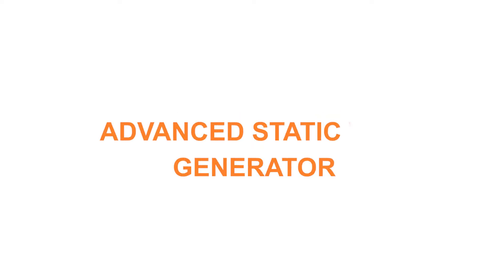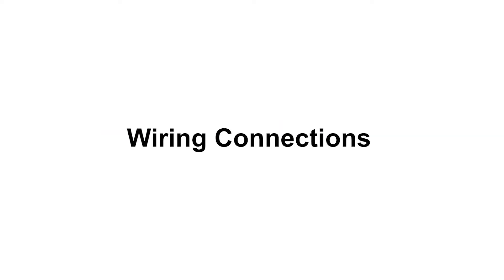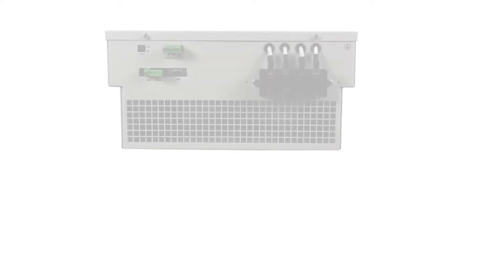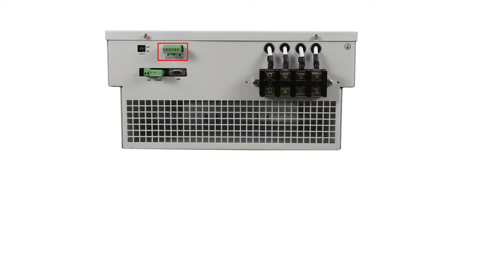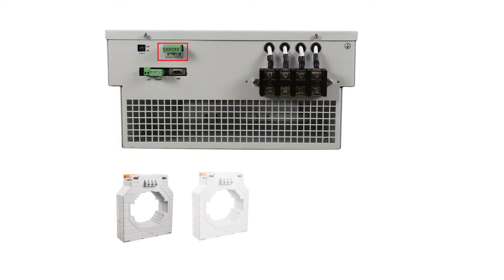Advanced Static VAR Generator — Wiring Connections. In the power side connectors, there are RYB and neutral. The lower side is meant for customer side connection for RYB and neutral, and earth will be connected here. In the control side, we have RYB, S1, and S2 — these 6 connections come from CTs connected at the customer end.